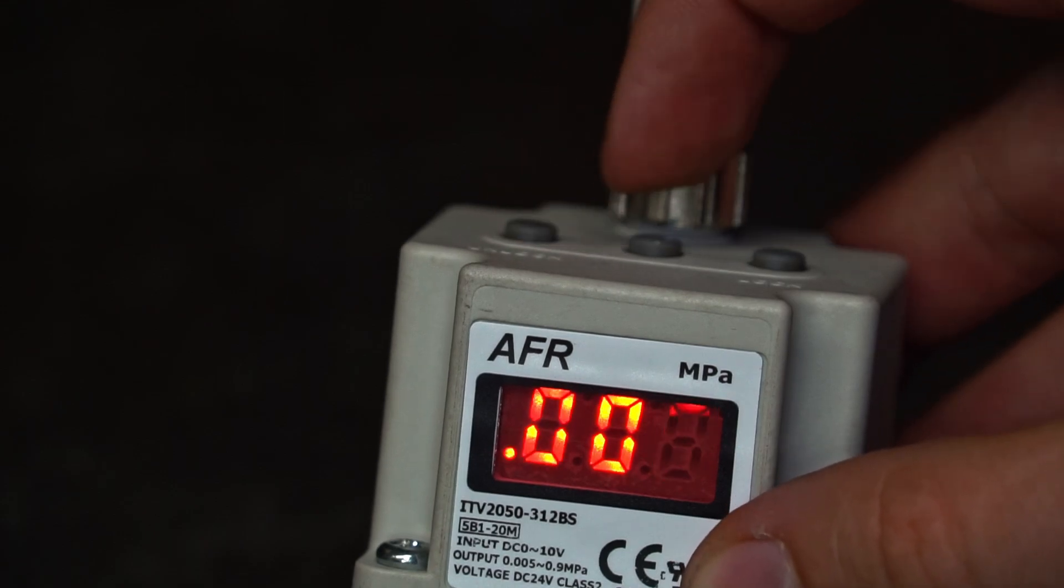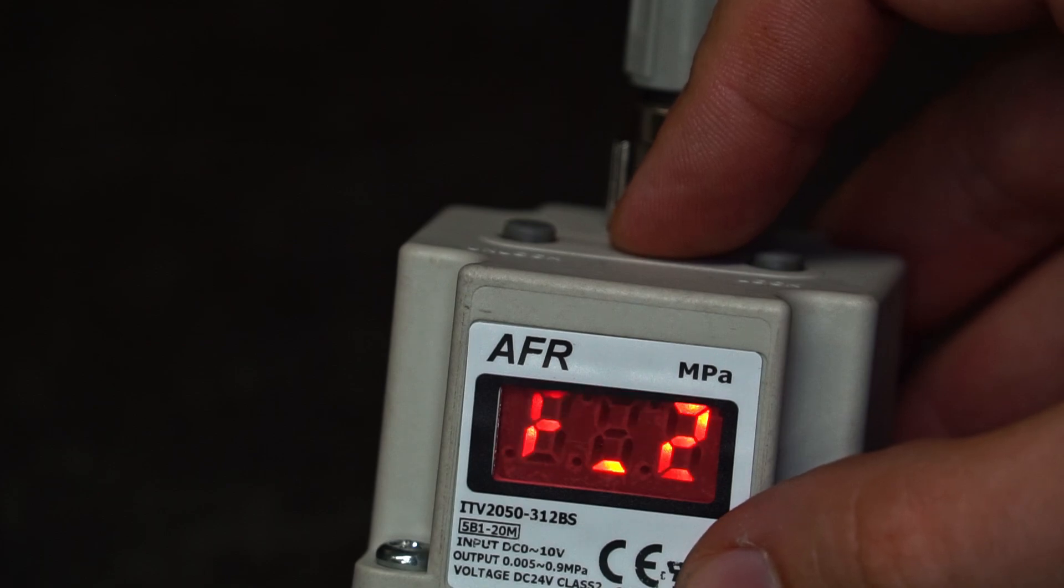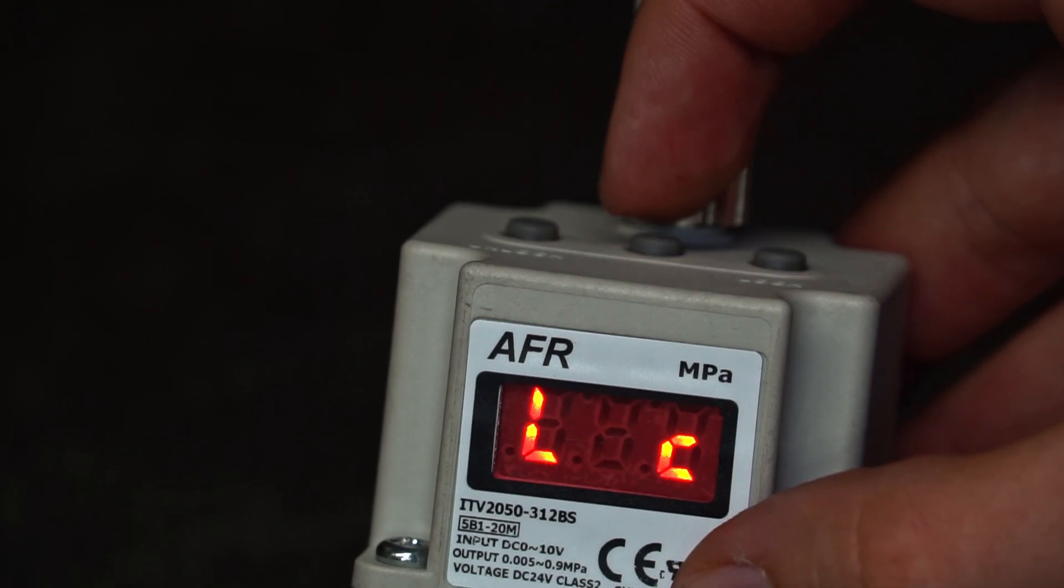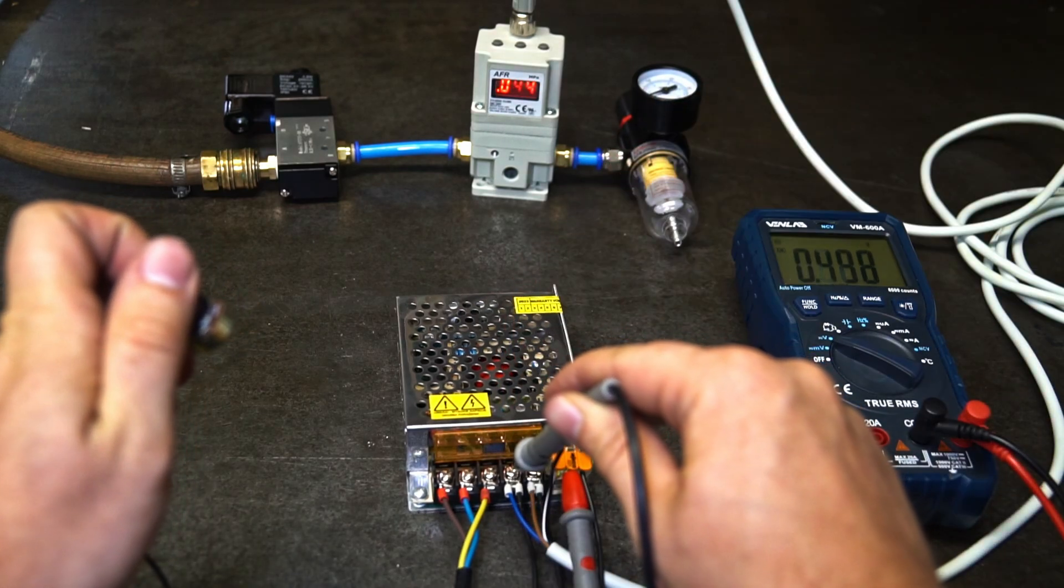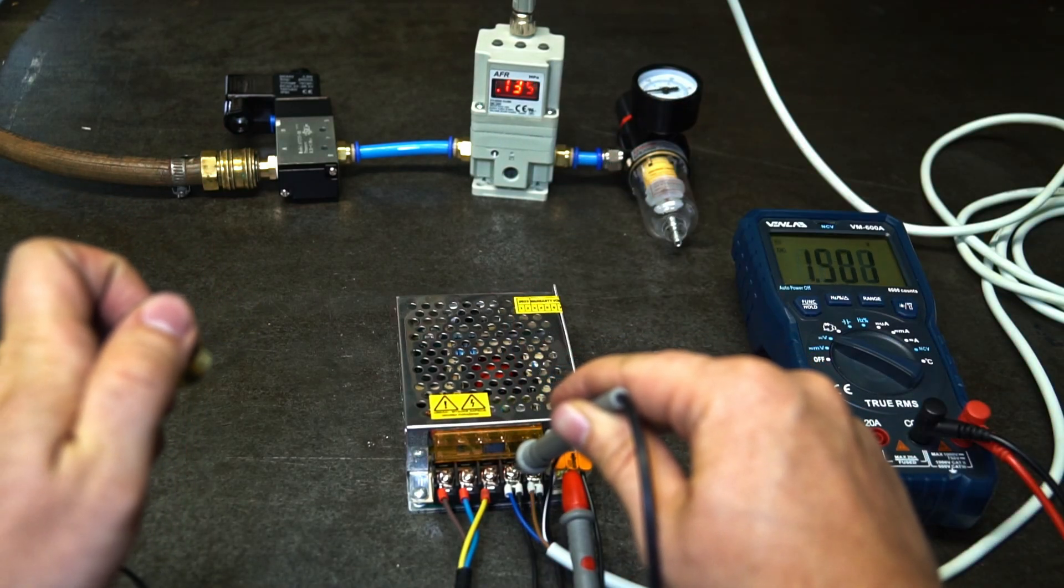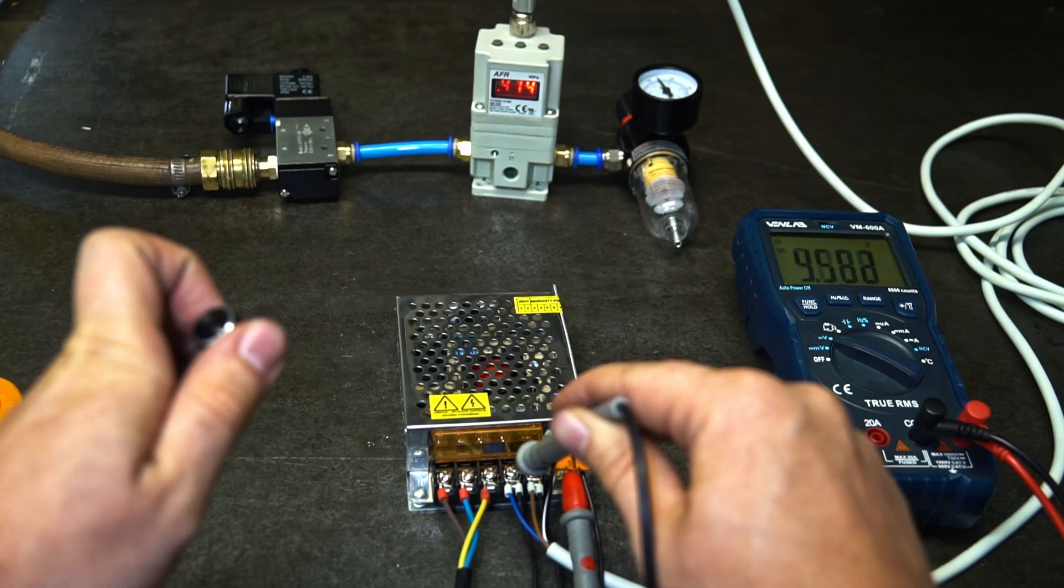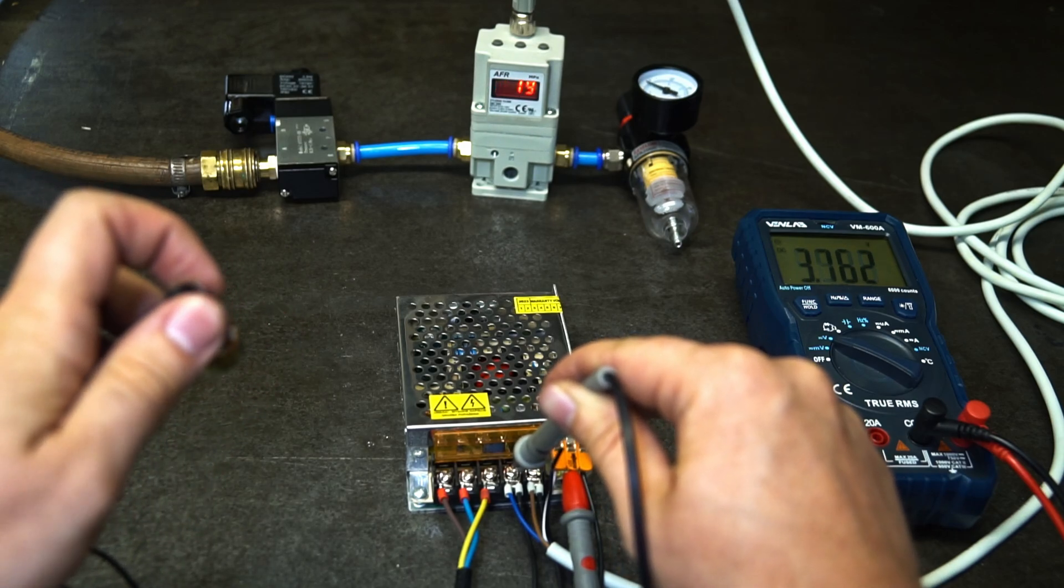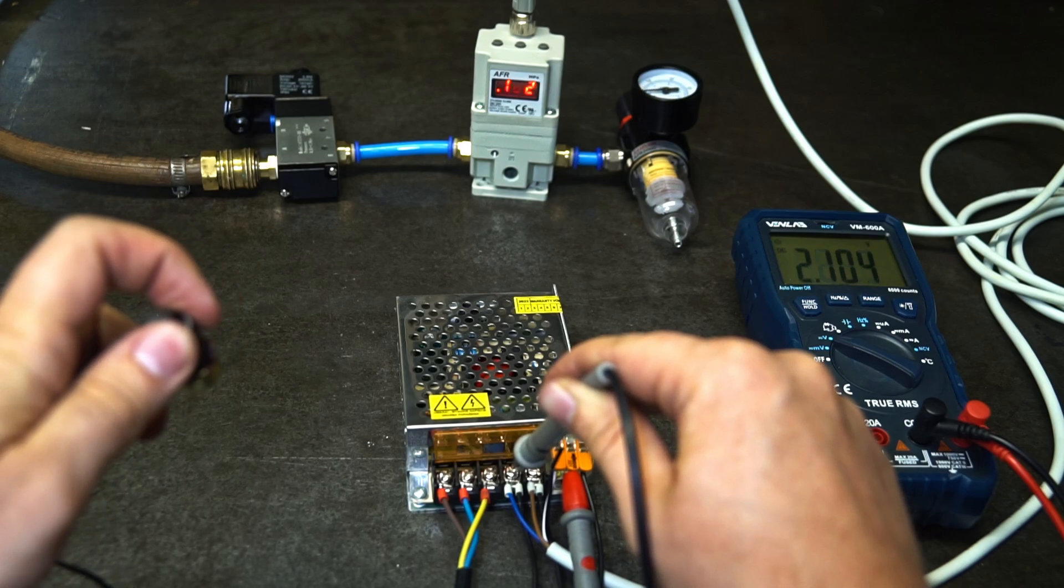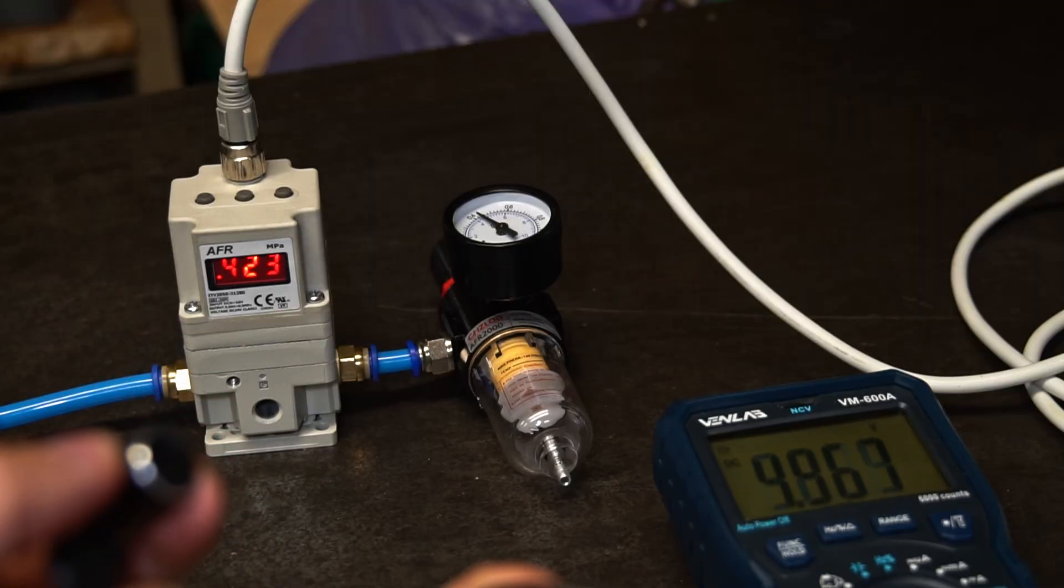I added a voltmeter to check what happens on the input signal. And here we go. The output pressure is proportional to the input voltage, but the range is a bit lowish.